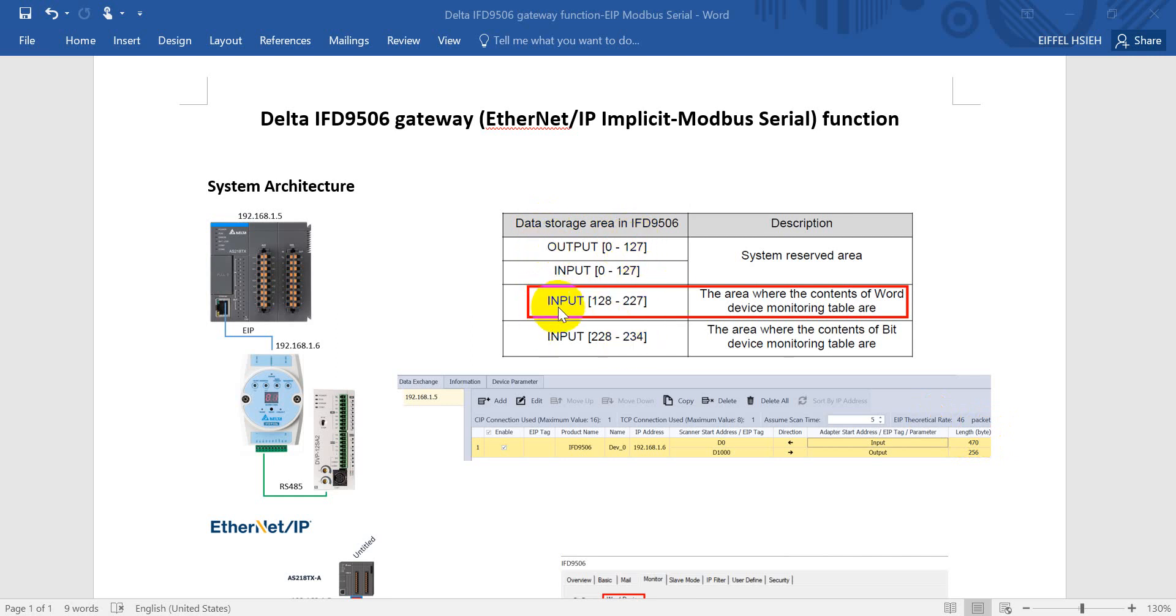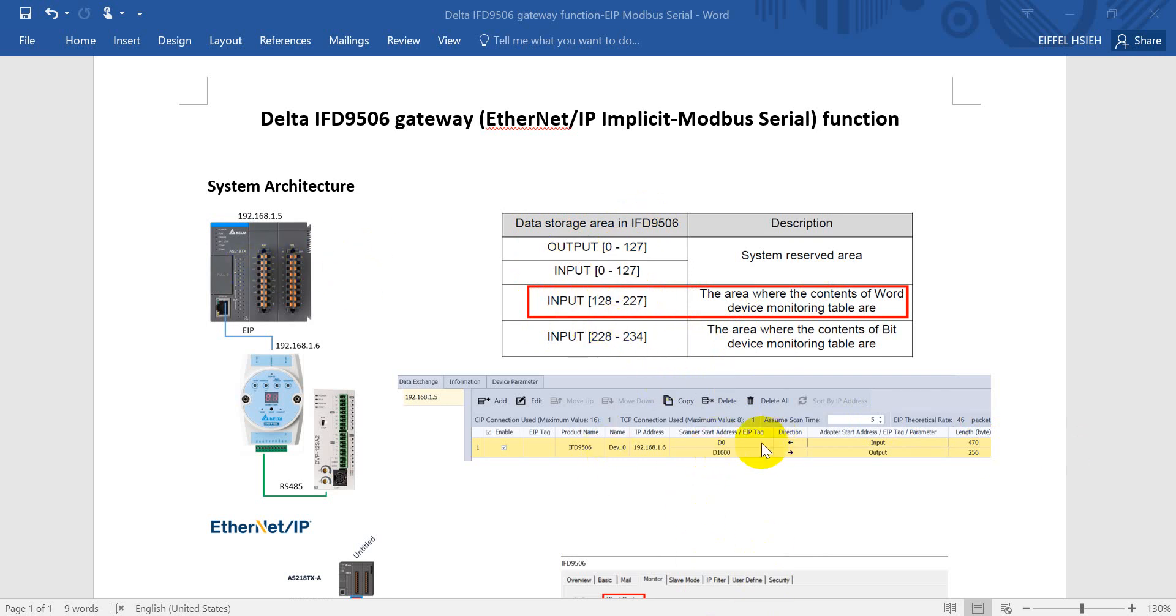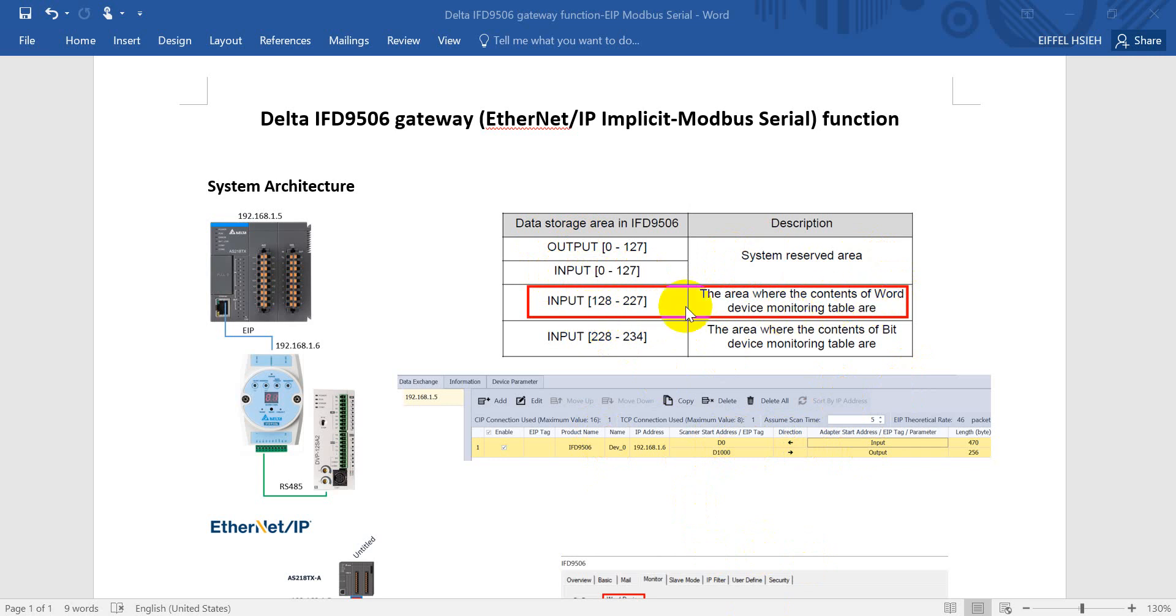And this topic will show you how to map the data to the input, meaning the information from IFD gateway will map to the PLC. So you can see here we will map the input data to 0, but as you can see the input will from 0 to 127 and this one is reserved for system. So the first word data will be mapped to 128.